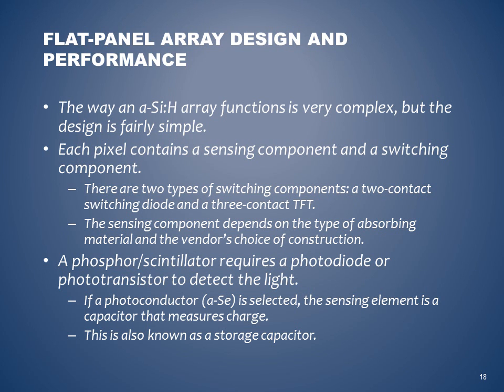Flat panel array design and performance. The way an a-Si:H array functions is very complex, but the design is fairly simple. Each pixel contains a sensing component and a switching component. There are two types of switching components: a two-contact switching diode and a three-contact TFT. The sensing component depends on the type of absorbing material and the vendor's choice of structure.